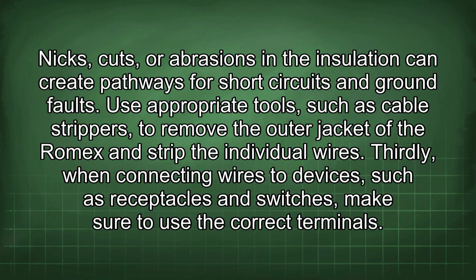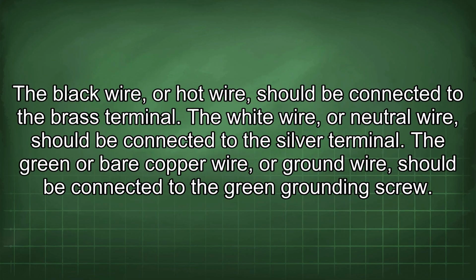Thirdly, when connecting wires to devices, such as receptacles and switches, make sure to use the correct terminals. The black wire, or hot wire, should be connected to the brass terminal. The white wire, or neutral wire, should be connected to the silver terminal. The green or bare copper wire, or ground wire, should be connected to the green grounding screw.